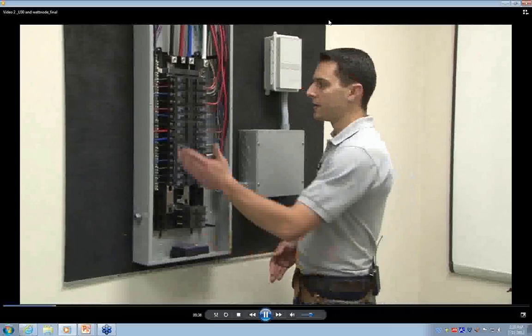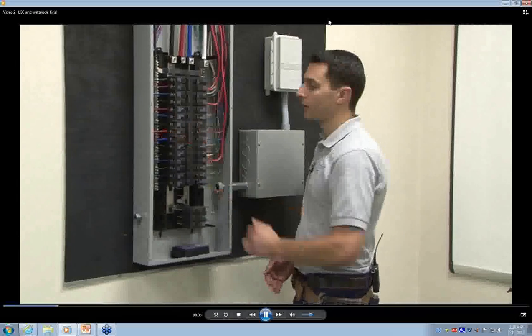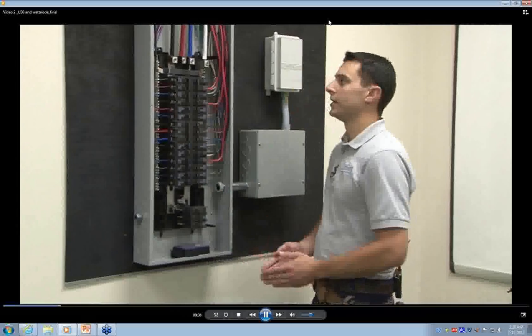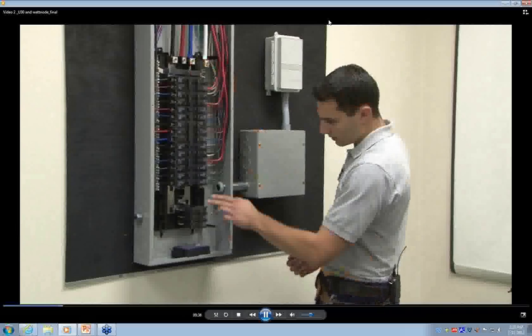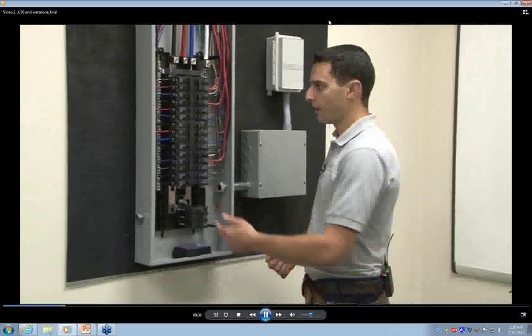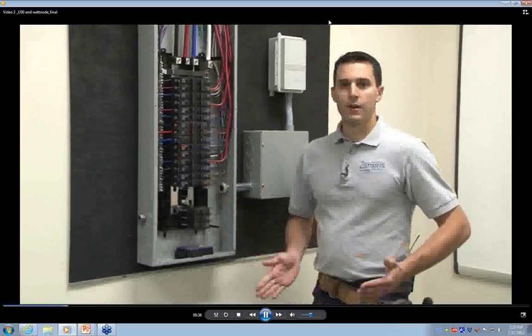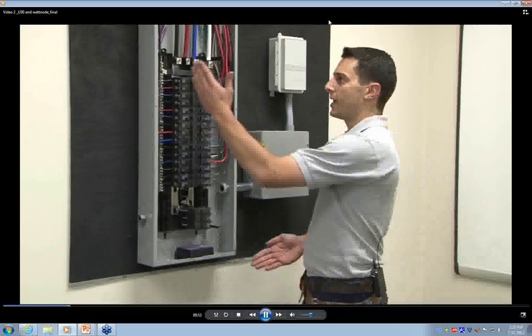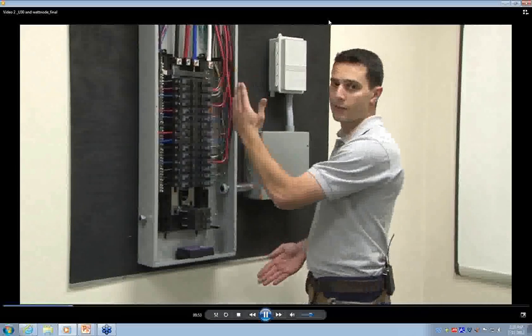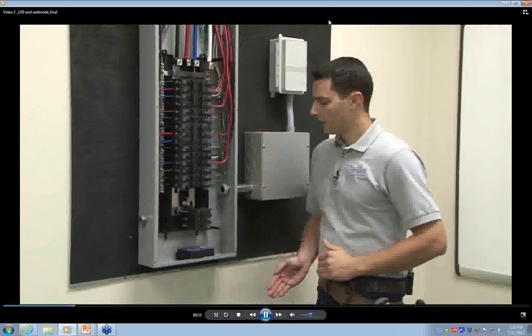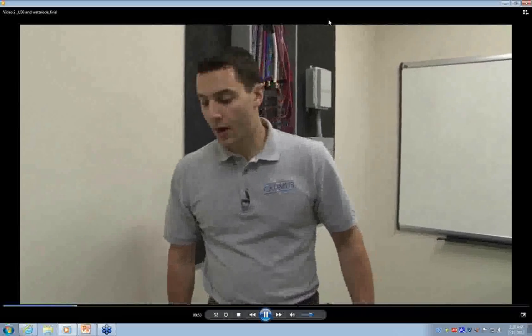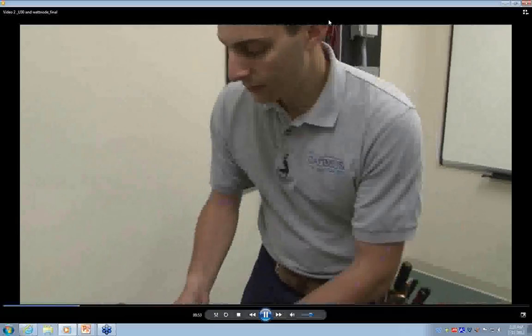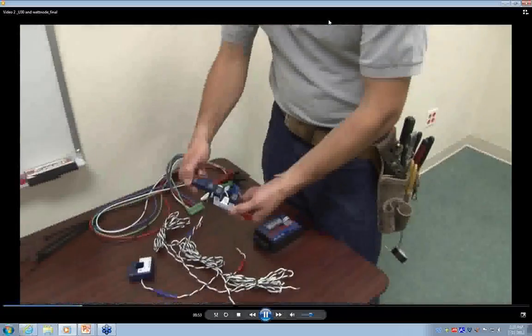We'll locate our CTs on these conductors for this 50 amp circuit, and our voltage leads can either go up here or down here, or if available, they can go on these conductors. These panel boards are wired phase A, B, and C, left to right, and top to bottom. We'll start by wiring our CTs to the watt node. We'll use a split core current transformer. Again, these are directional.